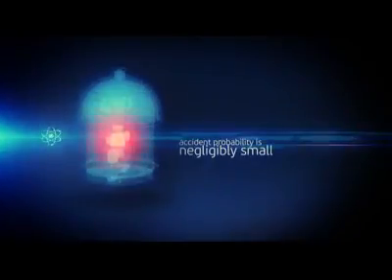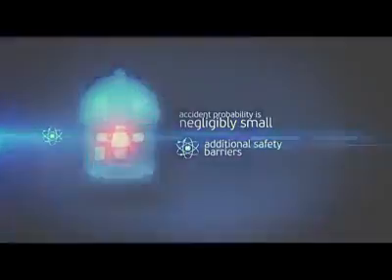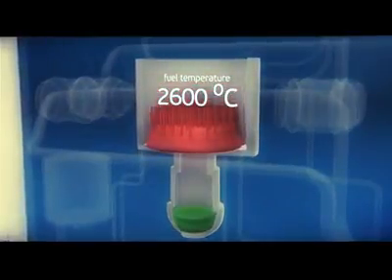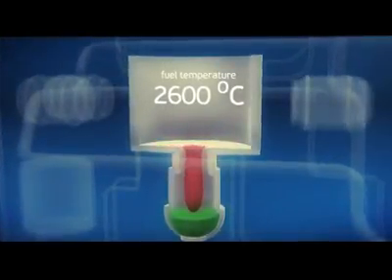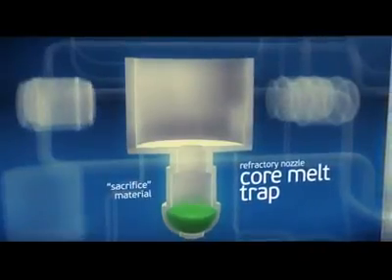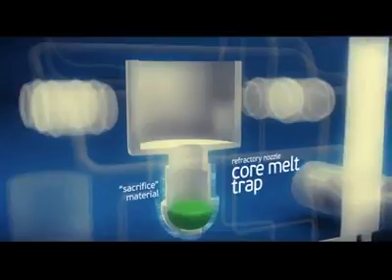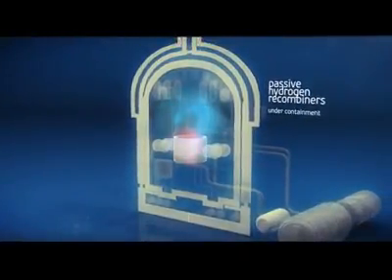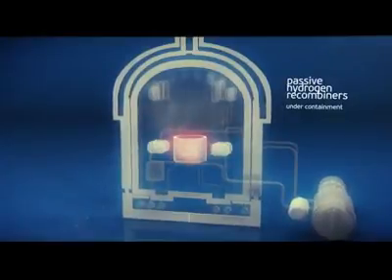The probability of an accident is negligibly low, and active and passive safety systems would confine it. Modern nuclear power plants are also fitted with additional safety barriers. If it is not possible to cool down the reactor core and fuel temperature rises to 2,600 degrees Celsius, the last line of defense is engaged — the reactor's pressure vessel bottom melts and remains of the nuclear fuel and reactor structures leak to the cooled refractory vessel called the core melt trap. It is filled with so-called sacrifice material which excludes a fission chain reaction and reduces the melt temperature. The trap provides for continuous cooling of the melt with cold water and does not allow it to destroy the shielding of the reactor hull. To rule out an explosion of hydrogen generated by the steam-zirconium interaction, passive hydrogen recombiners installed within the containment shielding are used. They accelerate the interaction of hydrogen and oxygen that results in water, so there is not enough time for gas to form an explosive concentration.